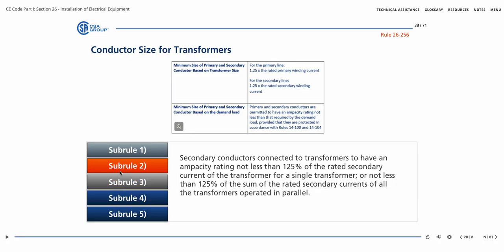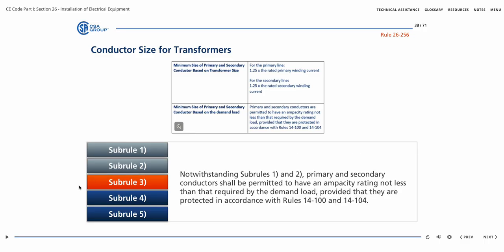Subrule 2 requires secondary conductors connected to transformers to have an ampacity rating not less than 125% of the rated secondary current of the transformer for a single transformer, or not less than 125% of the sum of the rated secondary currents of all the transformers operated in parallel. Subrule 3. Notwithstanding Subrules 1 and 2, primary and secondary conductors shall be permitted to have an ampacity rating not less than that required by the demand load, provided that they are protected in accordance with Rules 14-100 and 14-104.